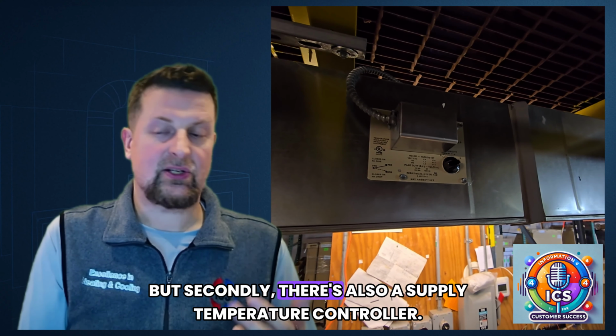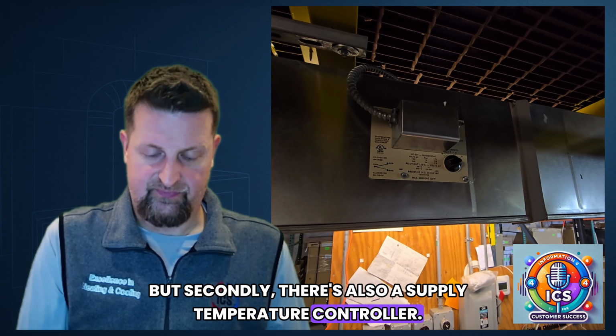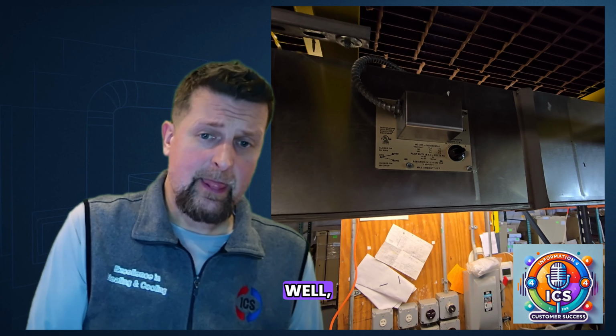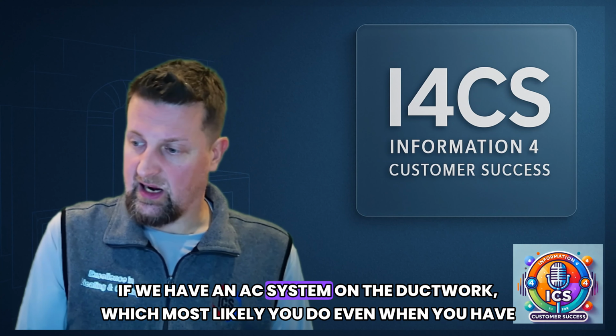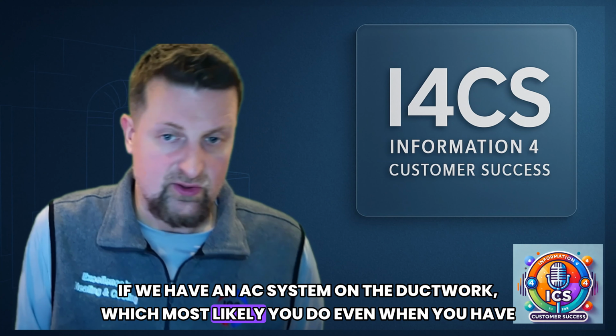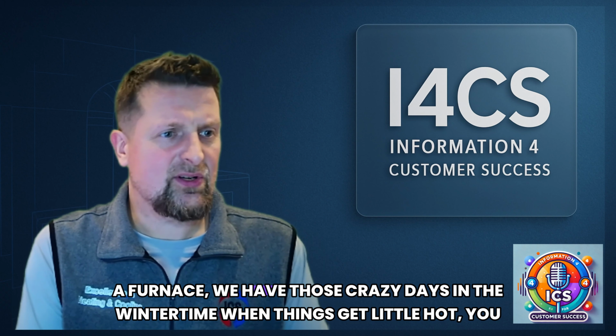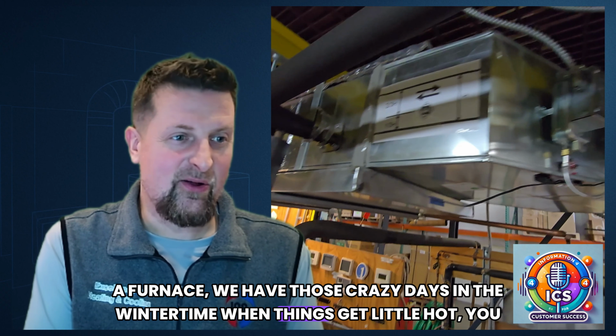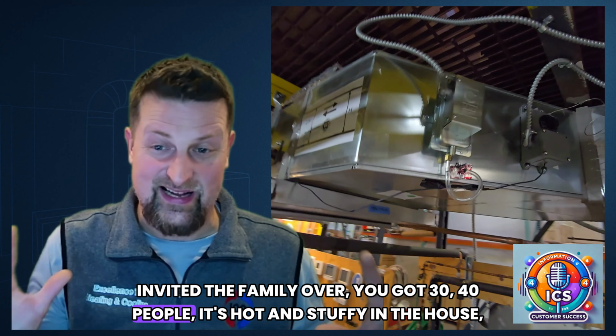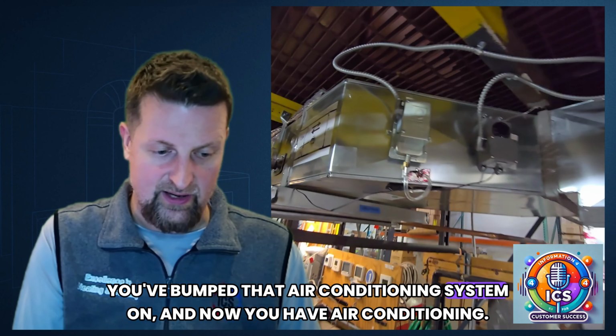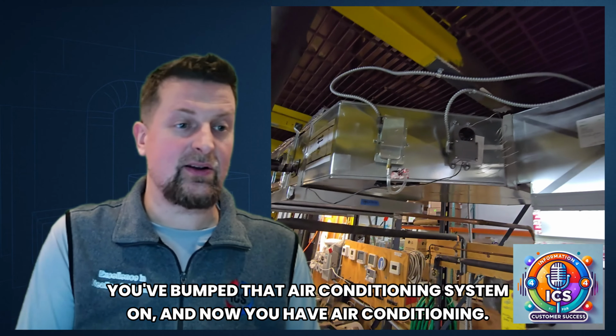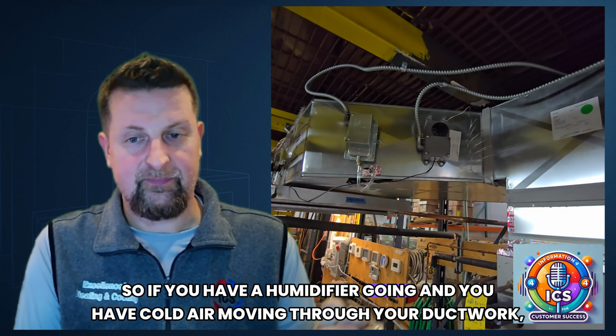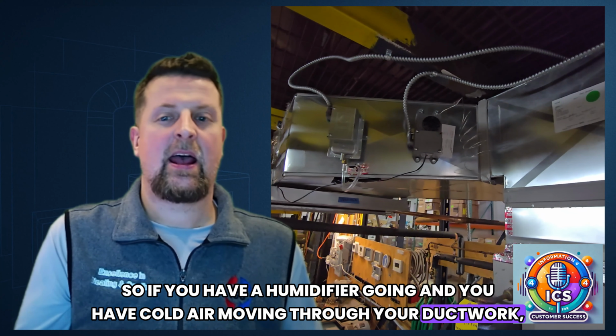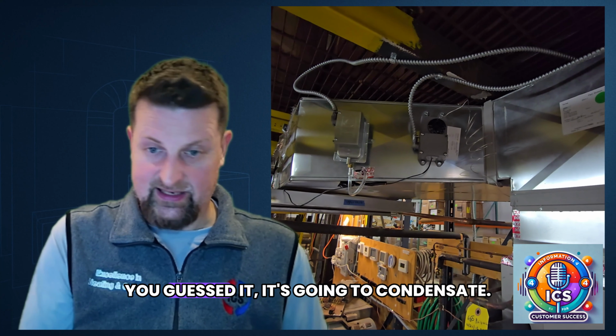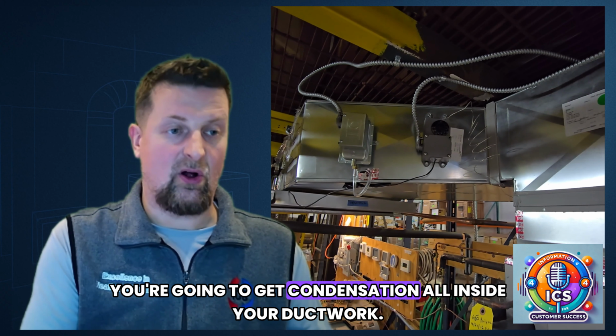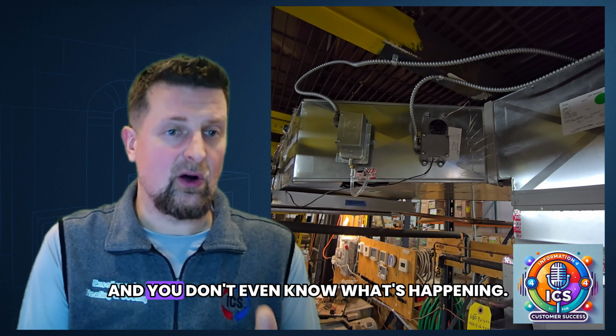So that's one controller that's above and beyond what most people do. But secondly, there's also a supply temperature controller. So what is that? Well, if we have an AC system on the ductwork, which most likely you do even when you have a furnace, we have those crazy days in the wintertime when things get a little hot. You invited the family over, you got 30, 40 people, it's hot and stuffy in the house, you bumped that air conditioning system on, and now you have air conditioning. Now, air conditioning is cold air. So if you have a humidifier going and you have cold air moving through your ductwork, what's going to happen? You guessed it, it's going to condensate. You're going to get condensation all inside your ductwork, and you don't even know what's happening.